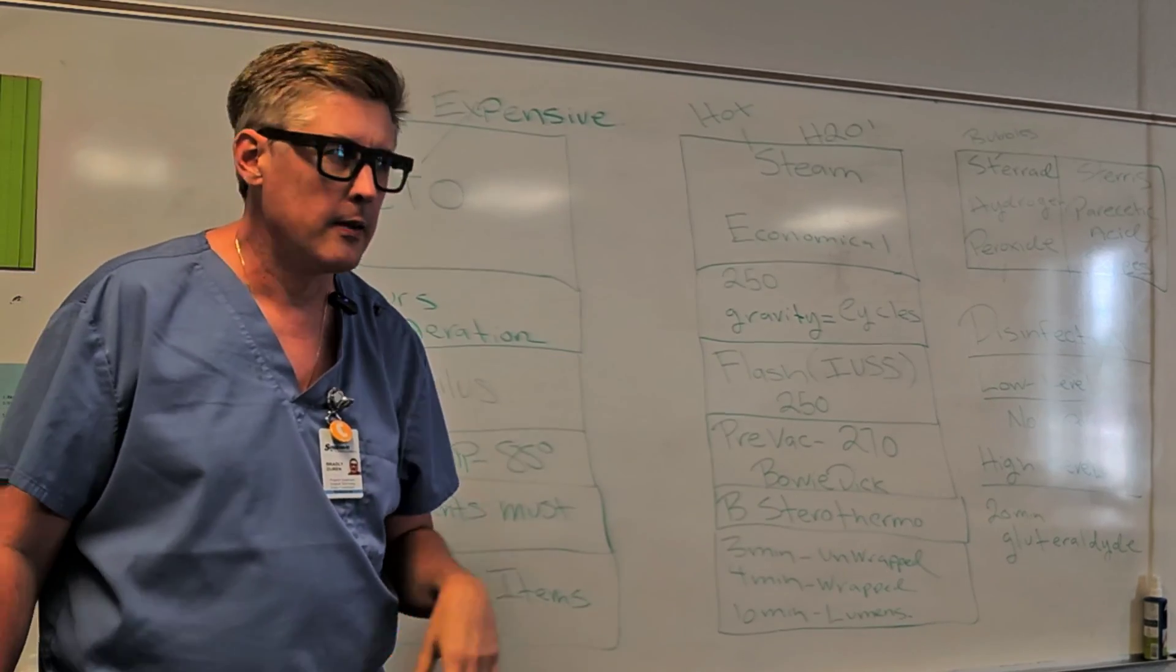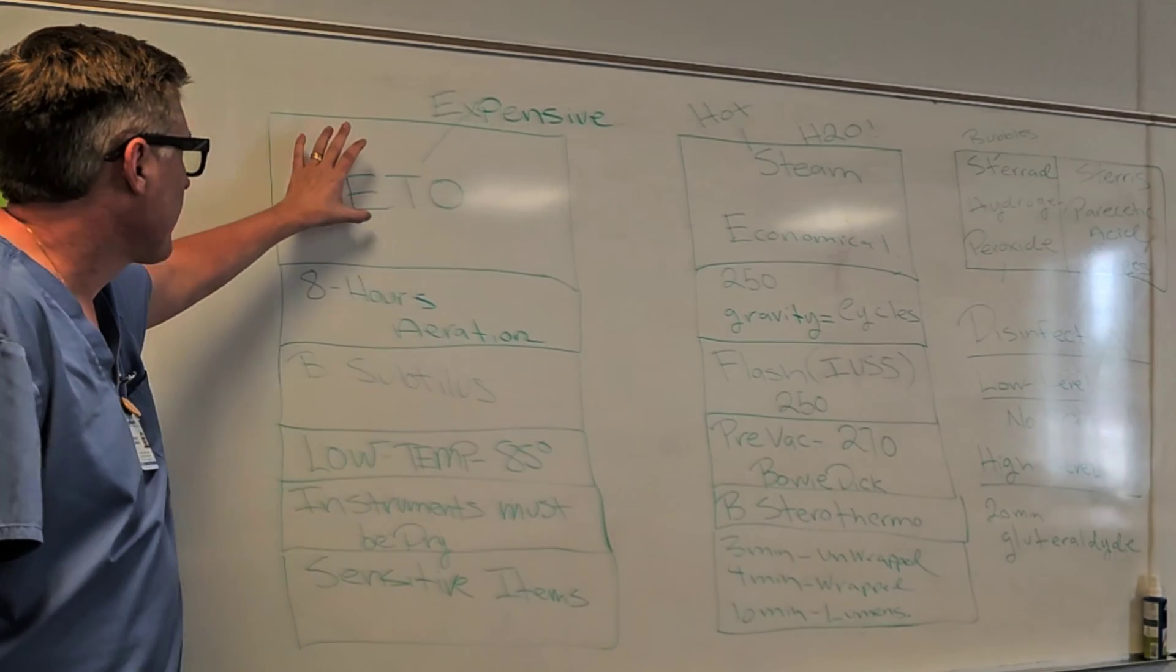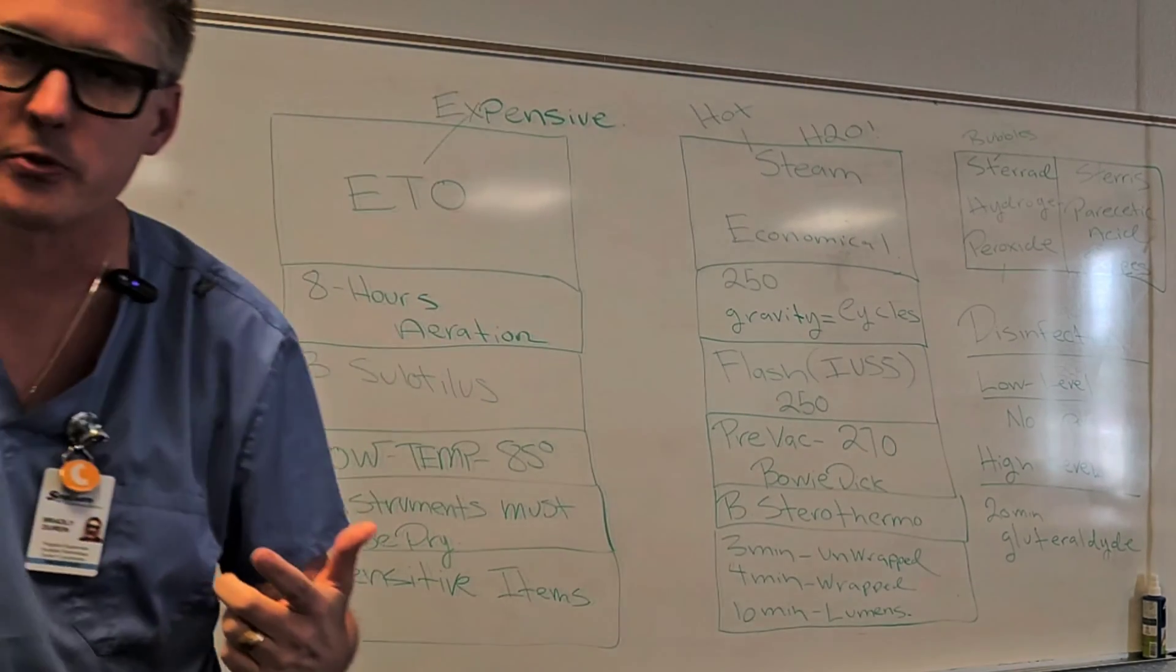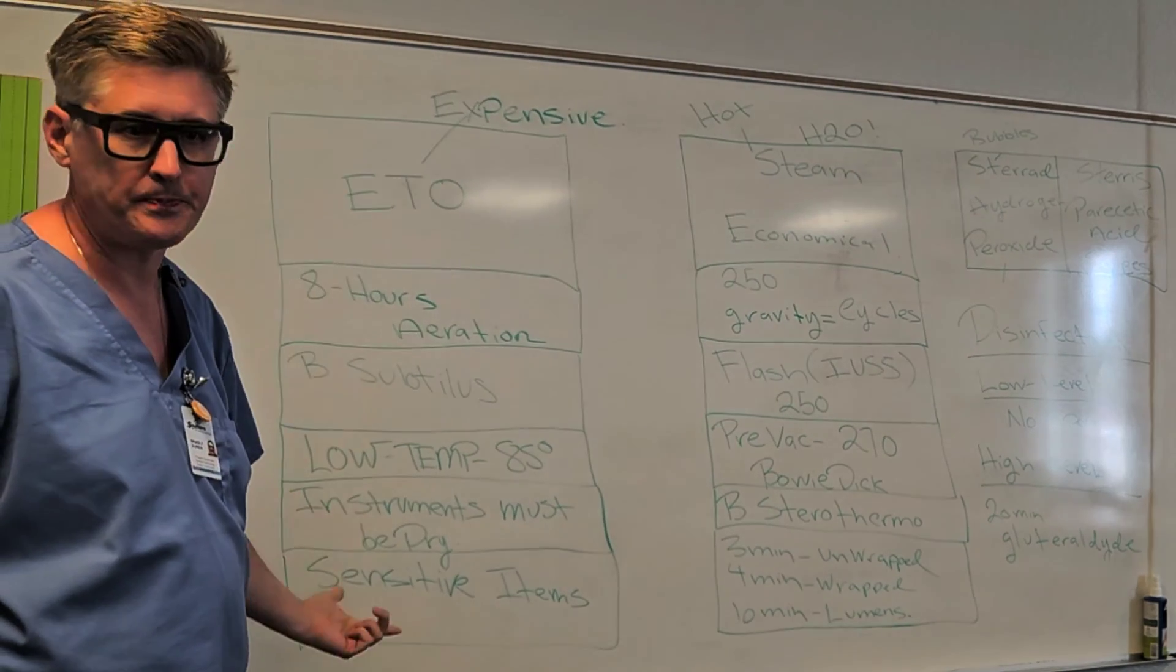It's used for sensitive items, right? Scopes, lenses, things that can't go in steam. And there's other processes for those also. But for right now, ethylene oxide was used for more sensitive items like scopes. So there's an expensive version of sterilization. And I probably have tons of questions on that, but we're going to jump right over to steam, the steam process of sterilization.